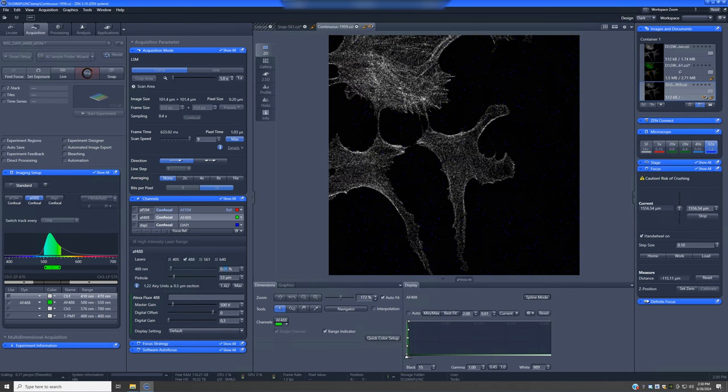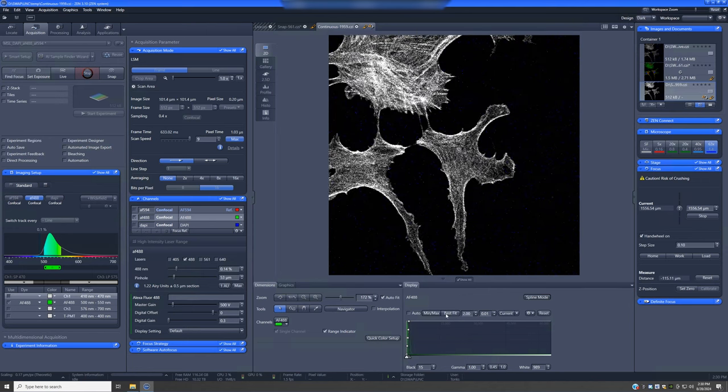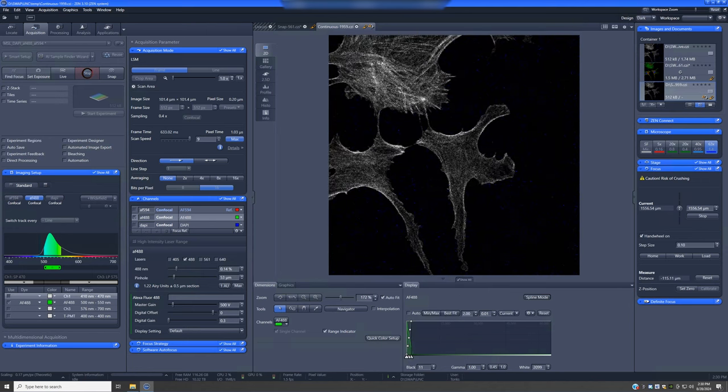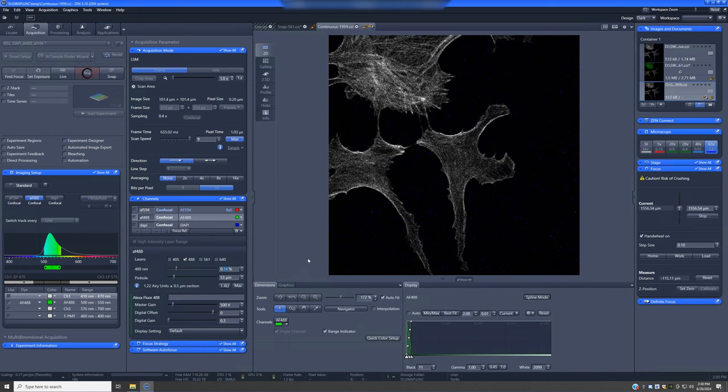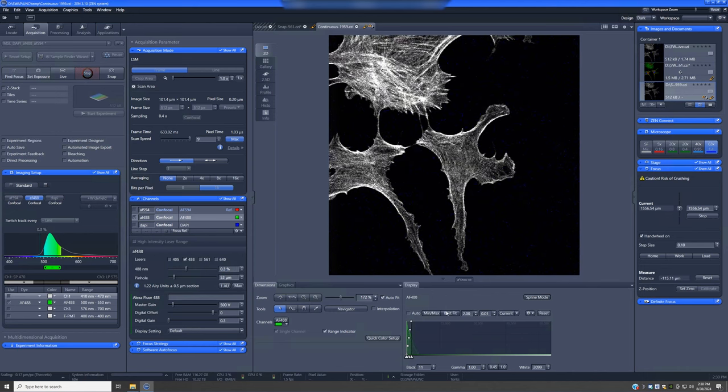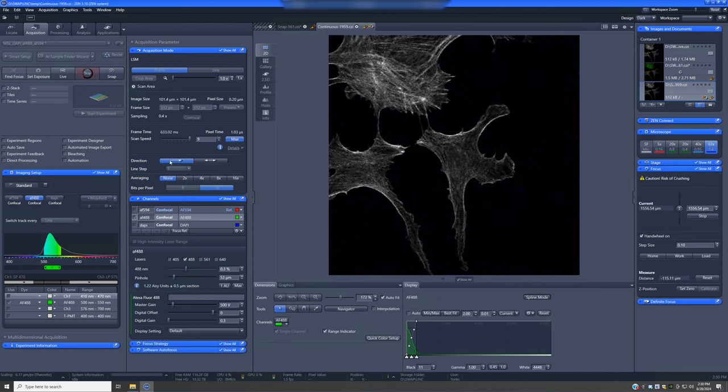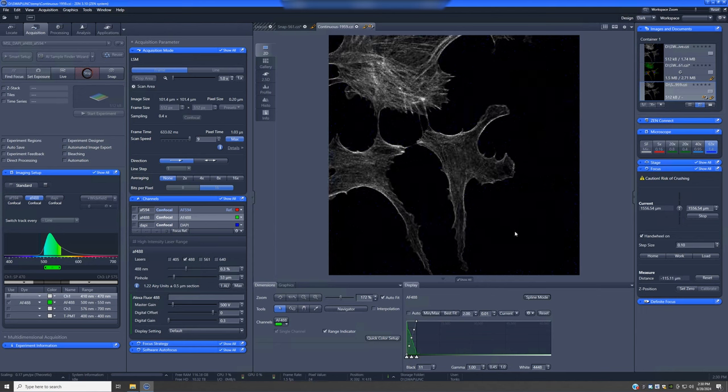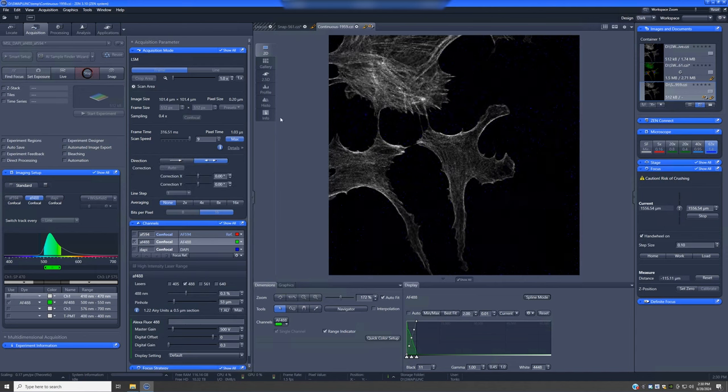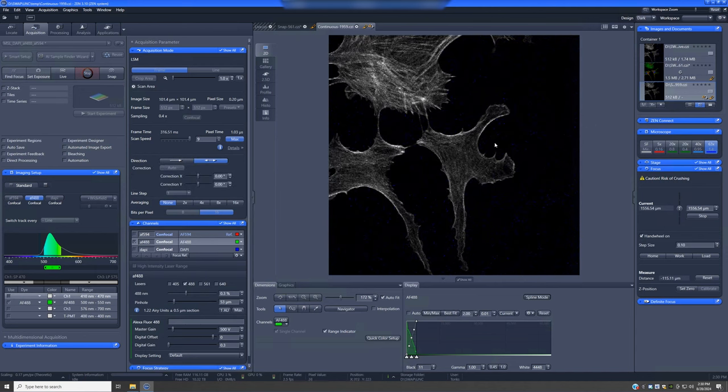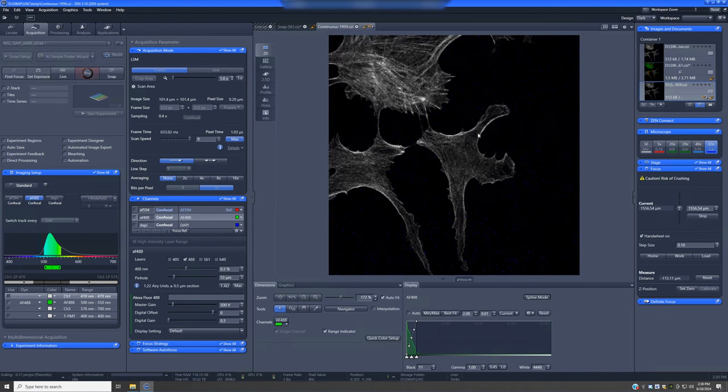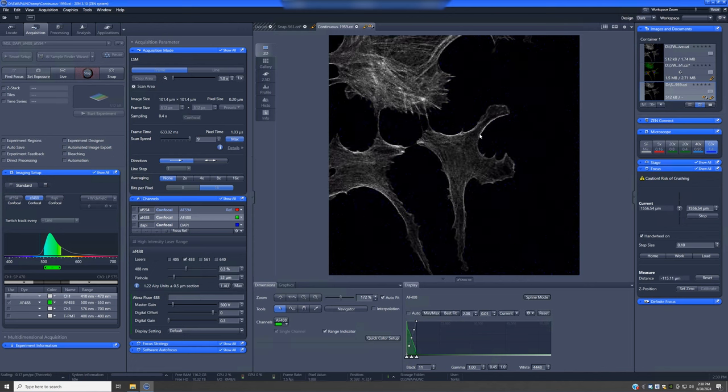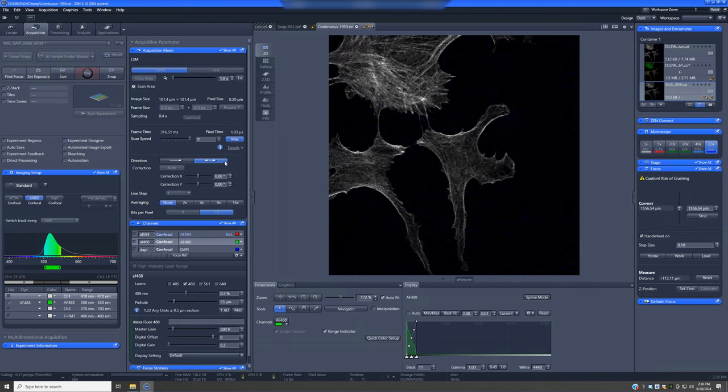One of the things that you want to do is image as quickly as possible. Right now, the laser is scanning in unidirectional mode, which is like a typewriter pattern through the image. We can make it scan in a snake pattern, and that will double the speed. However, sometimes when we do this, there are slight imperfections that appear in the image. So it's very hard to see these things, and it's sample dependent, zoom dependent, depends a lot on your imaging conditions. But sometimes there are sort of these jagged lines that appear in the image.